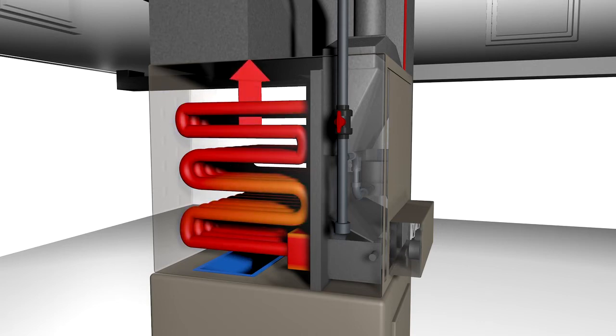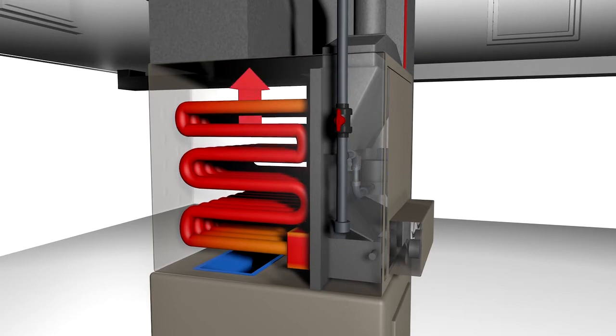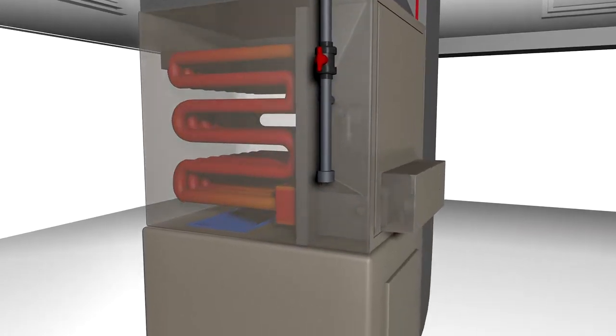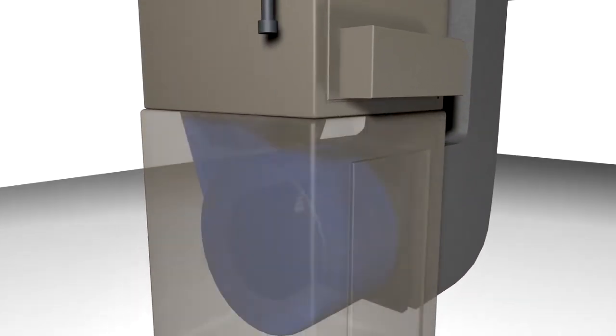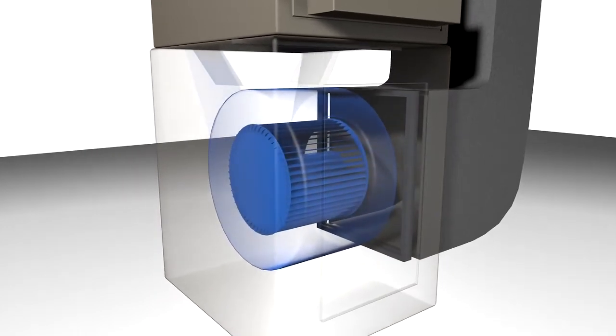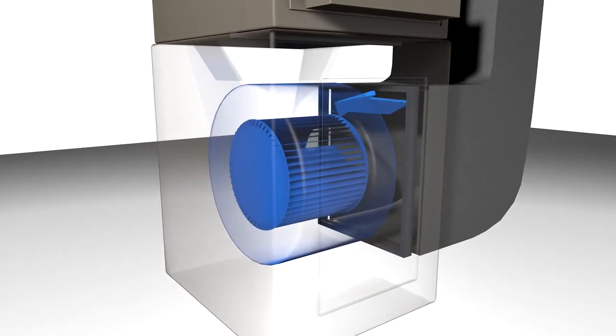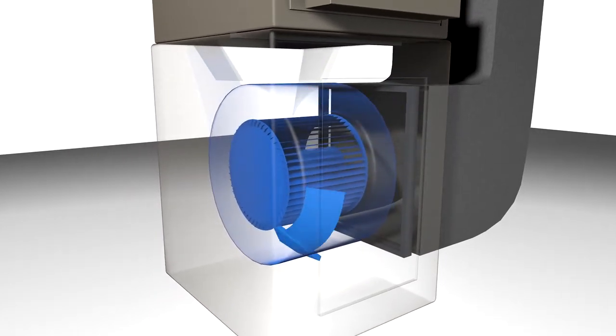These may sometimes be referred to as baffles. Various models will have different designs to slow down the air and promote heat transfer to the passing air. This is heated air that will be pumped into your ductwork and registers. The blower fan is the component that moves air coming into the unit from the cold air return ducts into the heat exchanger. It also forces the heated air throughout the ducts and registers of your home.